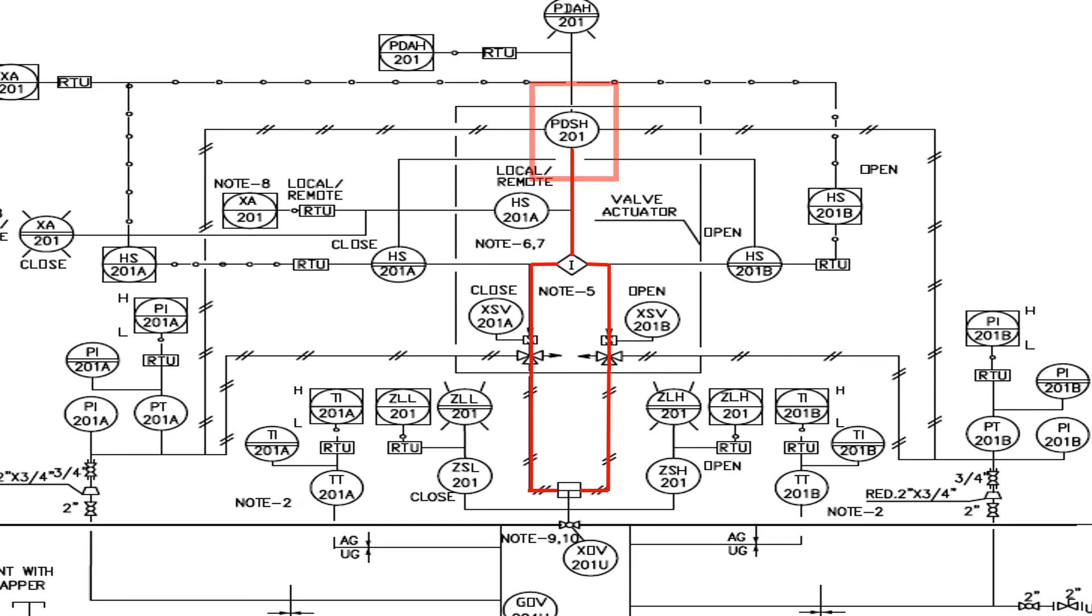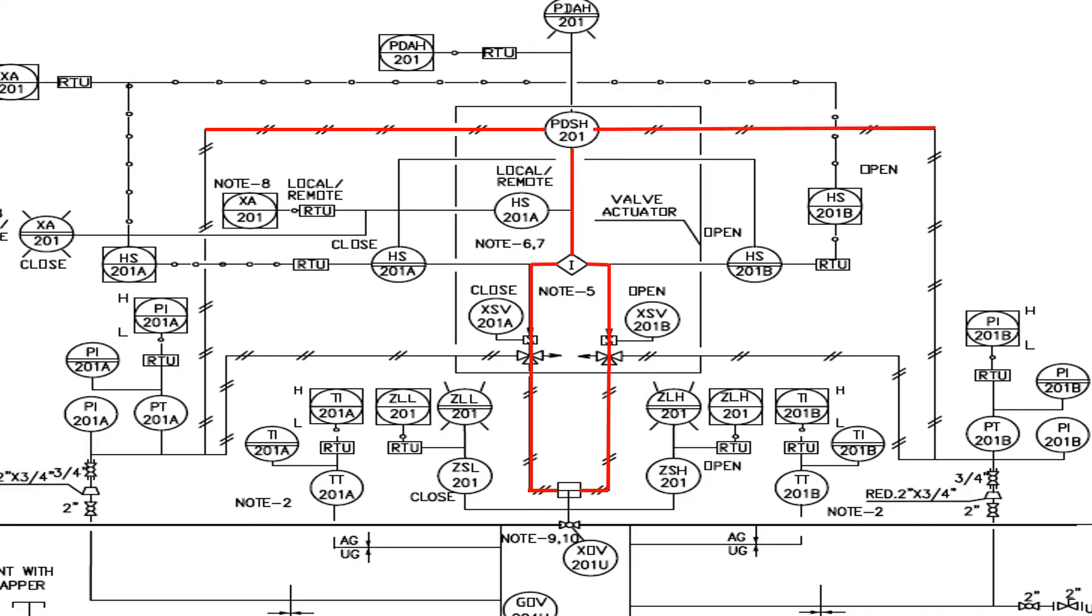Differential pressure switch is a device which utilizes a differential pressure to activate an electric switch. It is used to sense pressure difference between two points in a system.